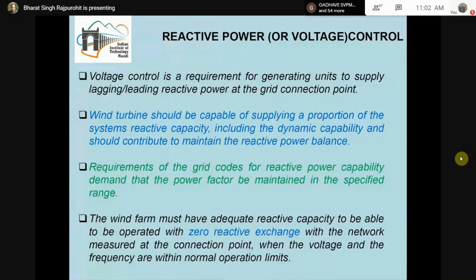But now there is an important question. We are able to see that in most wind energy conversion systems, an induction generator is used. An induction generator inherently is not able to generate reactive power. It requires reactive power from the grid to magnetize its air gap and for its operation. So how will an induction generator based wind energy conversion system be able to give reactive power instead of taking it? This question is addressed by using power electronic converters.